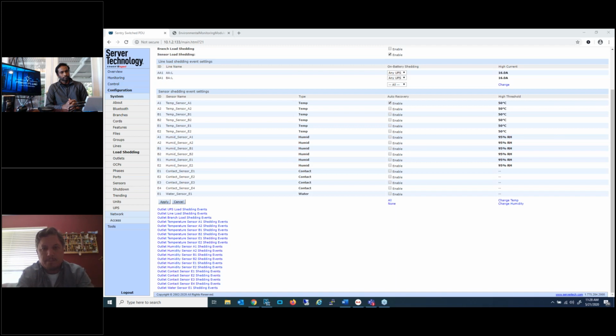And I've also had customers use smoke detectors. There are a number of smoke detectors that have a relay built in, so that the relay transitions from normally closed to normally open, or vice versa. That can be connected to a contact closure sensor that's with the optional environmental monitor control unit, and a smoke detector detecting smoke, indicating a potential fire, could switch off the gear automatically.